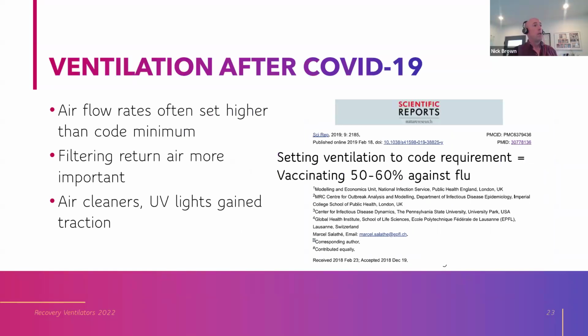What about COVID? Well, after COVID, many building owners, especially institutional building owners, set their airflow rates higher than code minimum. This is in recognition that higher ventilation rates do a better job of ensuring pollutants and germs are removed from the building. Filtering return air also became more important. So some buildings, if they were able to, upgraded from MERV 6 or MERV 8 return filters to 11 or 13. And some even installed air cleaners and UV lights to disinfect the air.